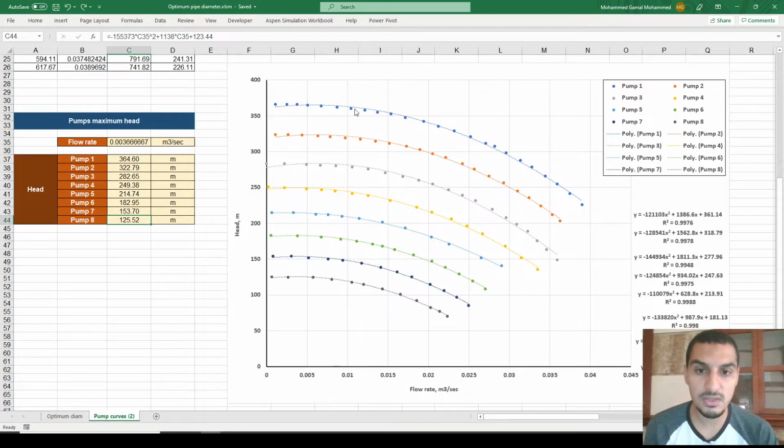You would see that the pump has a wide range of flow rates, and this is for almost all of them, and this is the case for centrifugal pumps, which have an impeller that rotates and gives energy to the fluid. As you see, the pump curve starts with a high head for low flow rate, and as you increase the flow rate, the pump head decreases a lot.